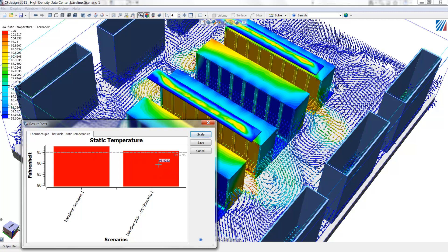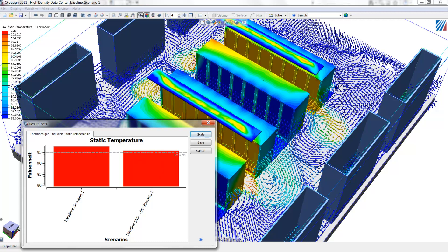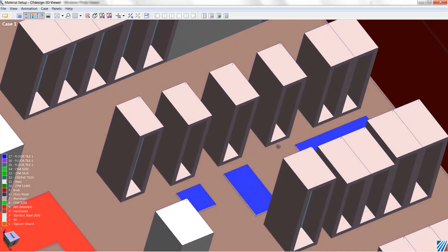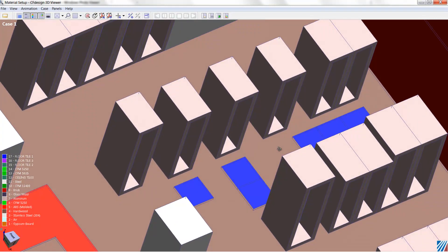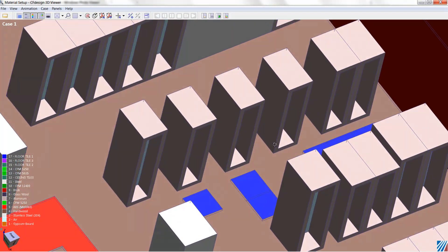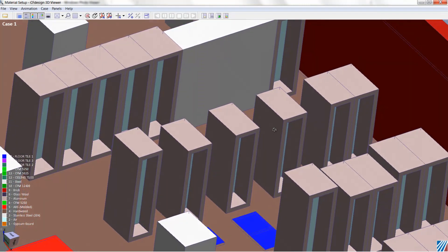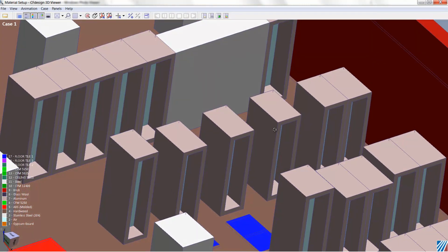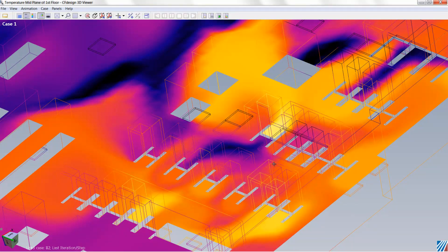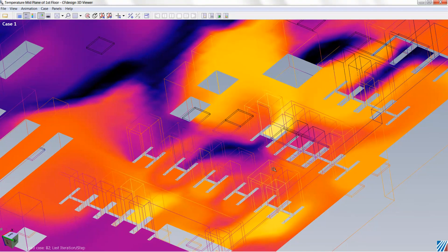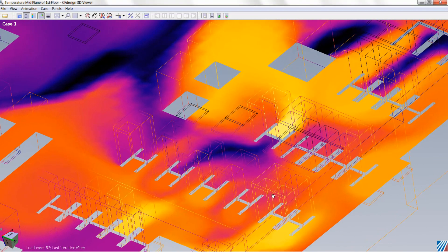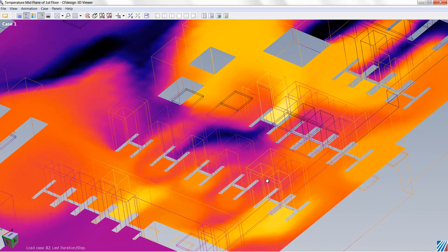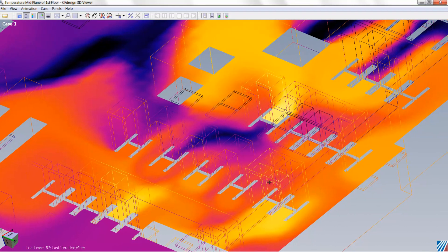CFDESIGN can also be used for data center retrofits. In older data centers, frequently, we don't have the standard, what's now standard hot aisle, cold aisle layout. So we may have racks that are staggered or offset from each other, so there are gaps between racks, where air can recirculate and lead to thermal runaway within the racks. The installation of blanking panels and baffle curtains can alleviate these effects.